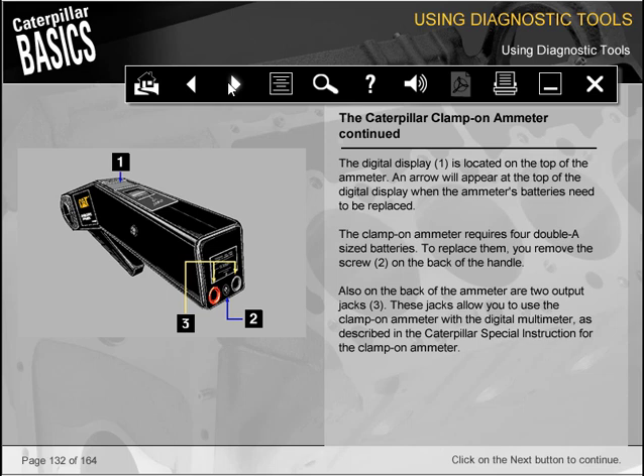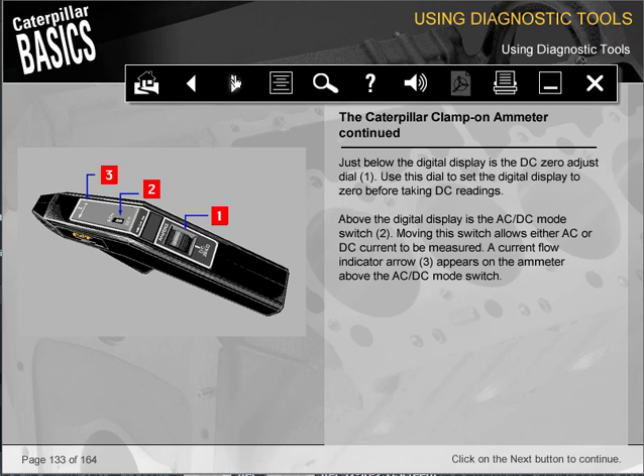for the clamp-on ammeter. Just below the digital display is the DC Zero Adjust dial, 1. Use this dial to set the digital display to 0 before taking DC readings. Above the digital display is the AC-DC mode switch, 2. Moving this switch allows either AC or DC current to be measured. A current flow indicator arrow, 3, appears on the ammeter above the AC-DC mode switch.